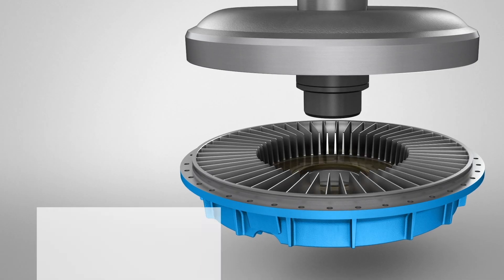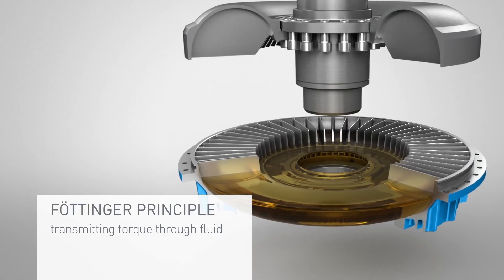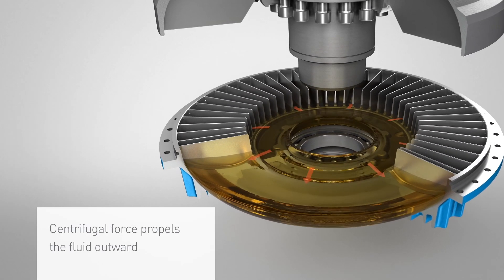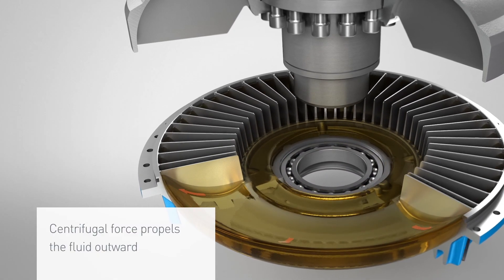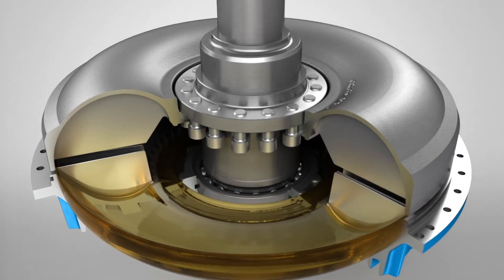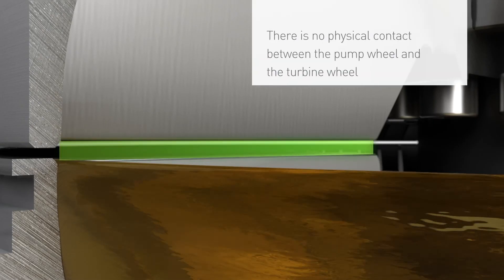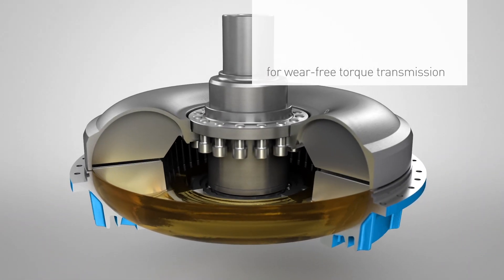The Fludex works according to the Föttinger principle. This means that the torque is not transmitted mechanically, but rather through a liquid medium, usually oil. In the initial situation, the rotation of the pump wheel generates the centrifugal force that propels the fluid outward. The slow motion depiction shows a process that actually takes place within a fraction of a second. There is no physical contact between the pump wheel and the turbine wheel. As a result, the torque is transmitted without any wear.